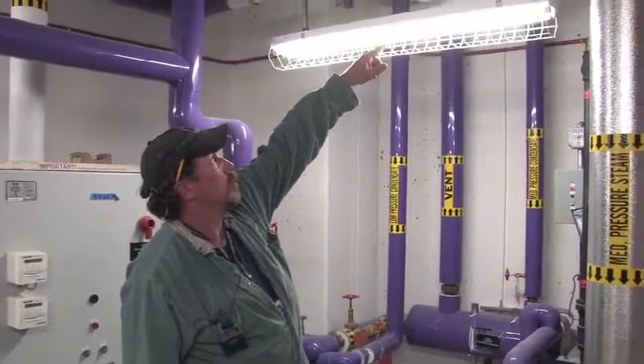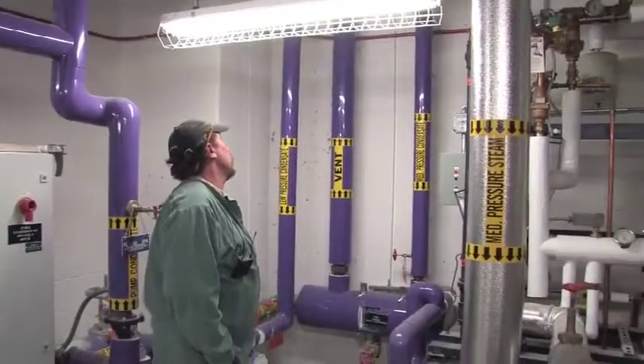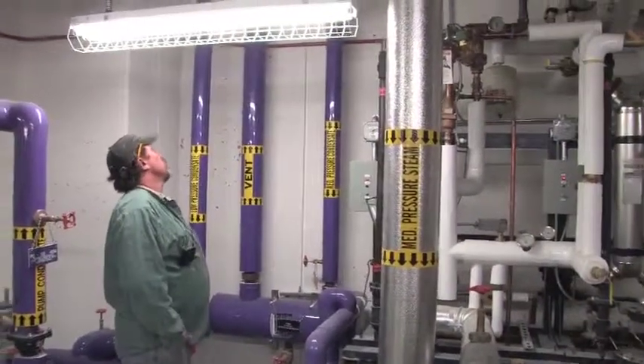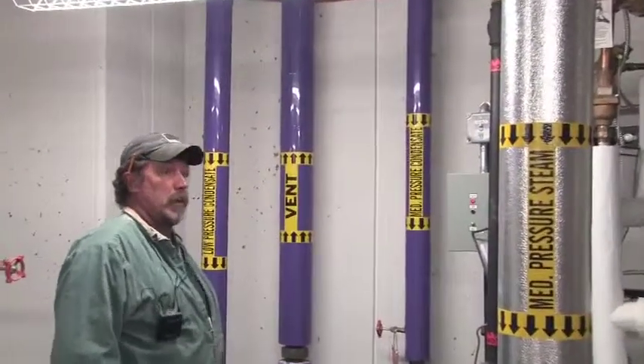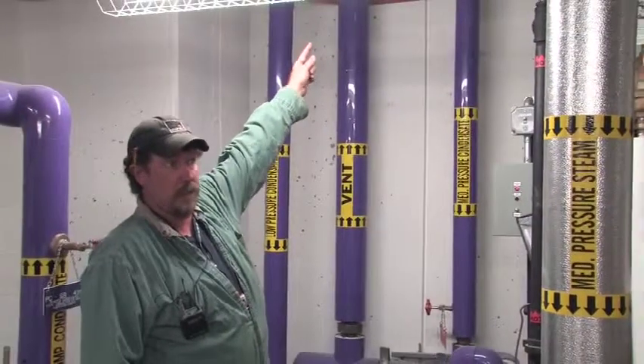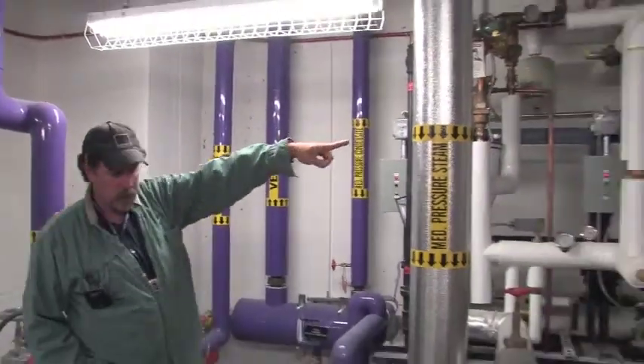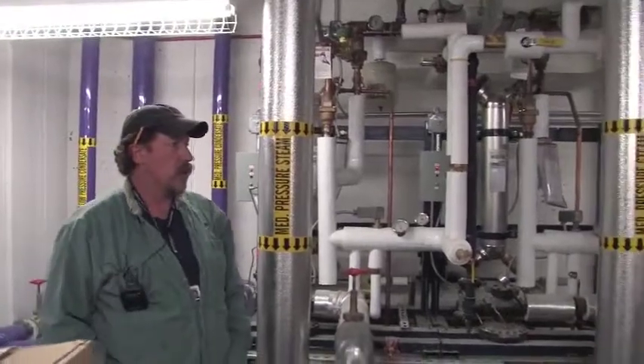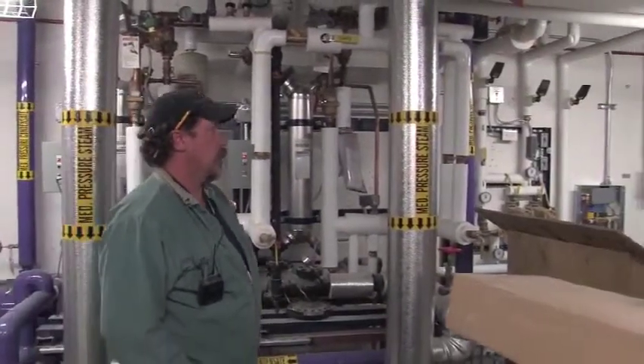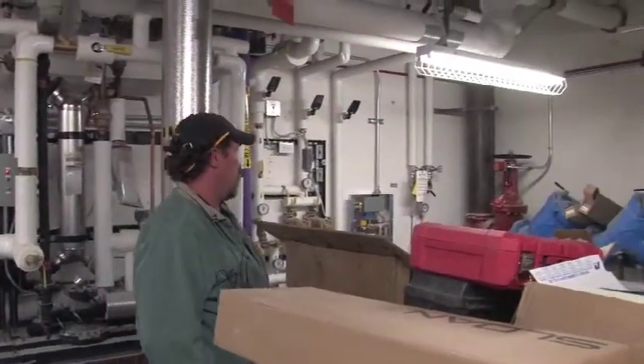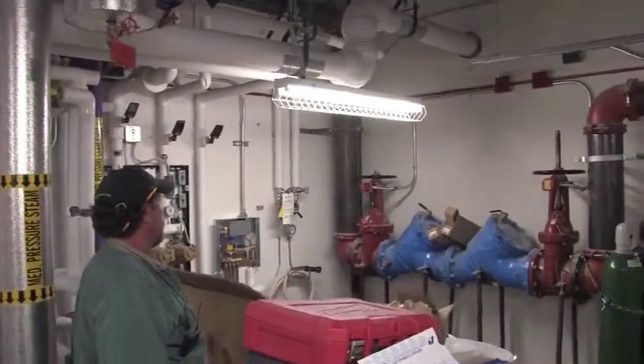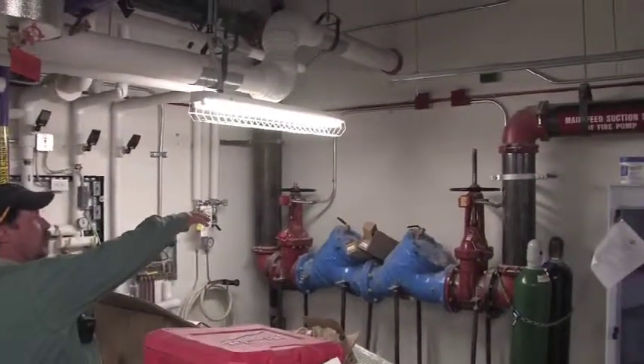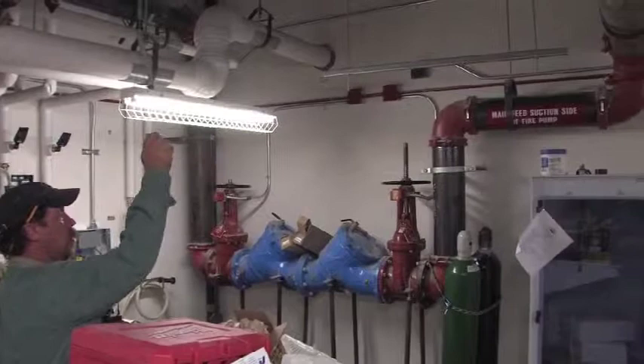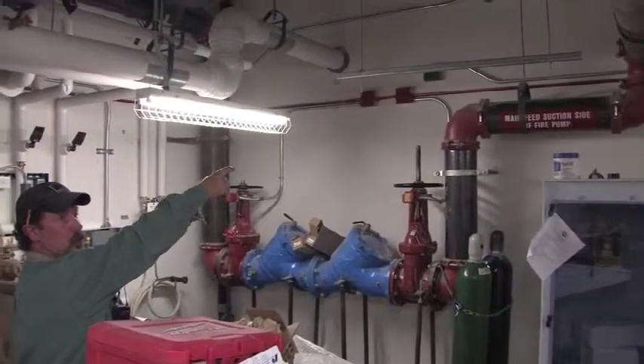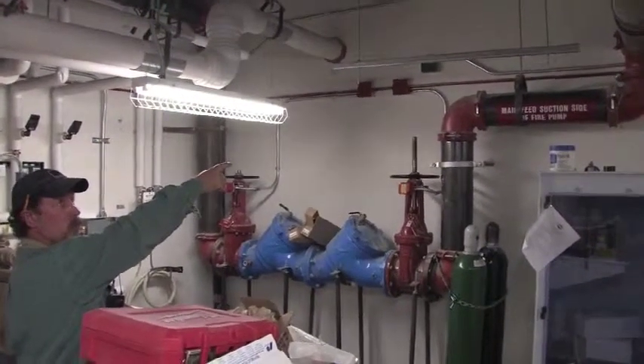Right up here is an OS&Y valve. It's an 8-inch OS&Y. That's the main feed for this building right here, coming in off the street. And it heads right over here to your backflow preventer. You got a couple of 8-inch OS&Ys on either side of them. And that's your feed side for the fire pump. Goes through the wall into the fire pump room.